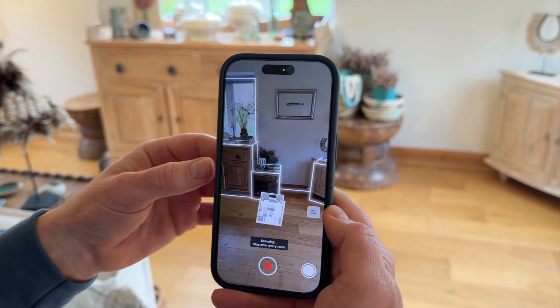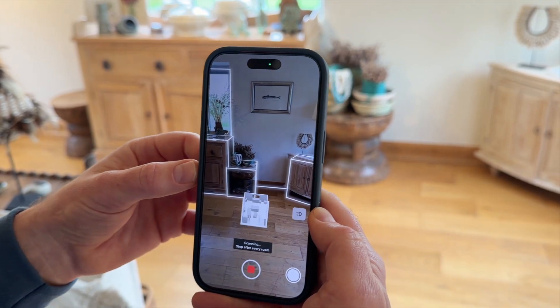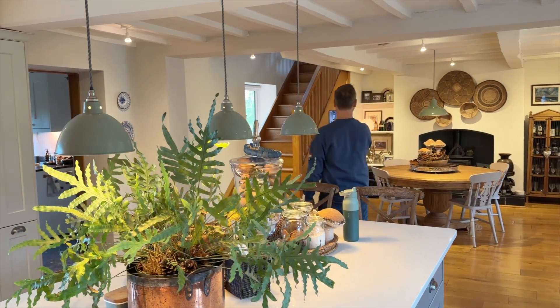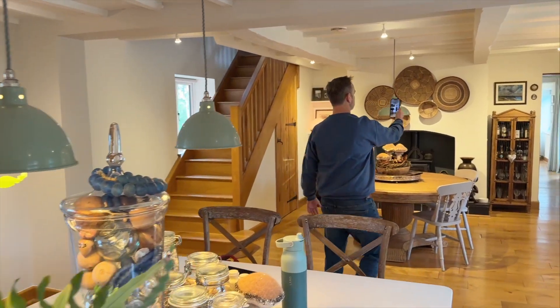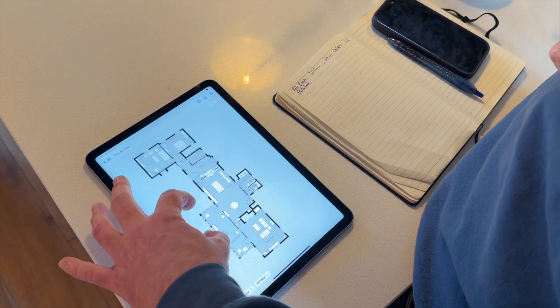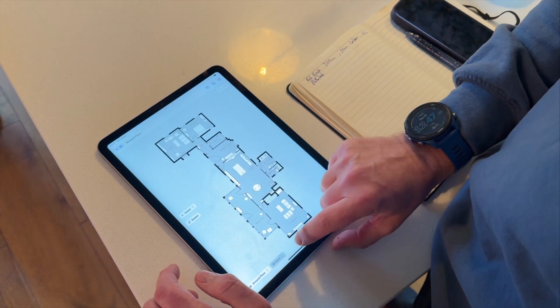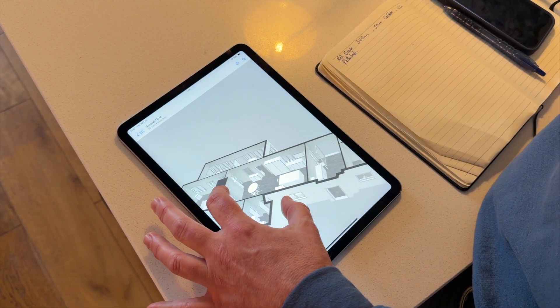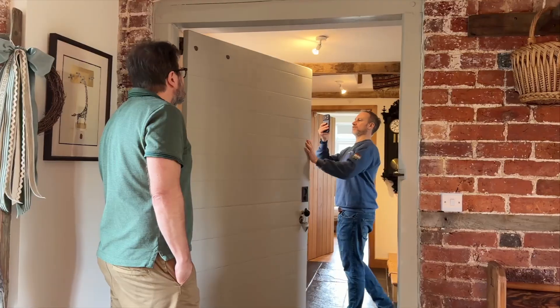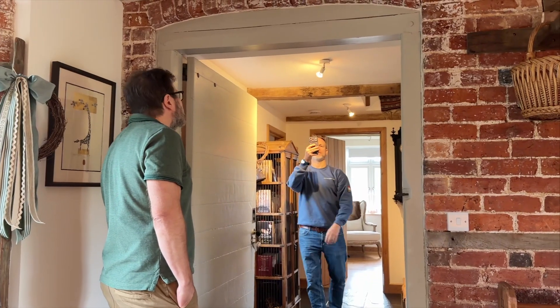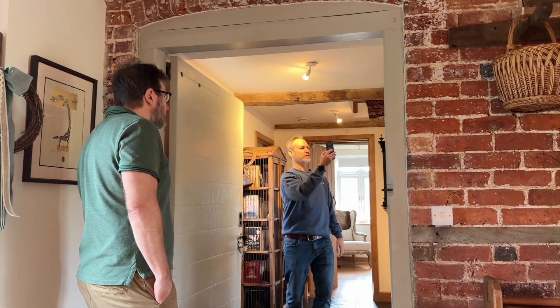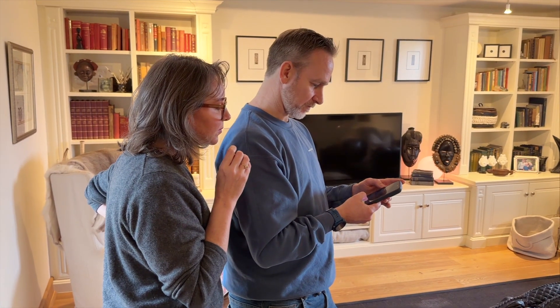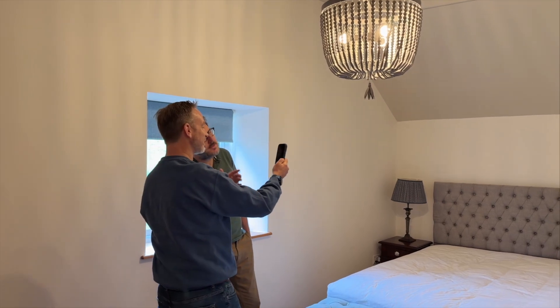Starting out doing a room-by-room heat loss calculation, first port of call is: which tool am I going to use to capture the dimensions for each individual room - the windows, the doors, the floor areas? It creates a 3D image of each room and they stitch all the rooms together, and then we can use those dimensions to extract into the software for our room-by-room heat loss calculation. Then we move on to building materials, which are really important because they give us a U-value - a number that tells us how much thermal energy can be lost through that wall. Having a build-up of each independent building material, whether it's a wall, window, floor, or ceiling, is critical.